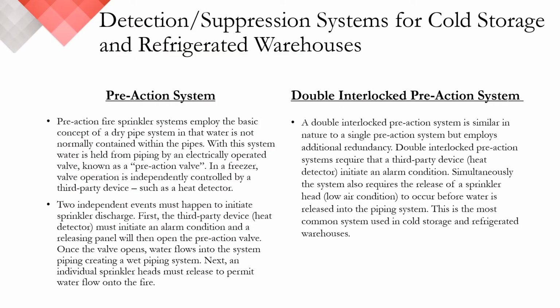This is most likely a review for most of us on the webinar today, but before we go into any details, we need to cover the basics. Most refrigerated or freezer warehouses have either a pre-action system or a double interlocked pre-action system. In both cases, the sprinkler pipes do not contain water. As we all know, water freezes at 32 degrees Fahrenheit or 0 degrees Celsius. While there are a variety of definitions available to explain the differences between the two systems, the basic summary is this. Pre-action systems utilize a dry pipe sprinkler system, and when an initiating device, such as Protectowire, initiates an alarm condition, a valve is electronically opened and water flows into the sprinkler pipes.